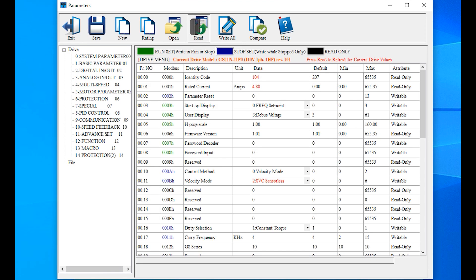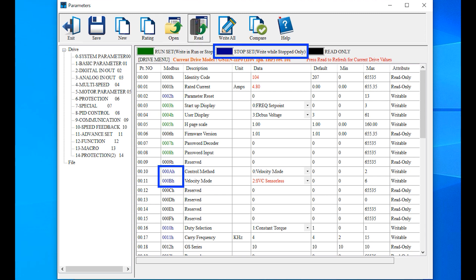Parameters with green Modbus addresses can be written to while the motor is running, blue can only be written when the motor is not running, and black are read-only parameters.